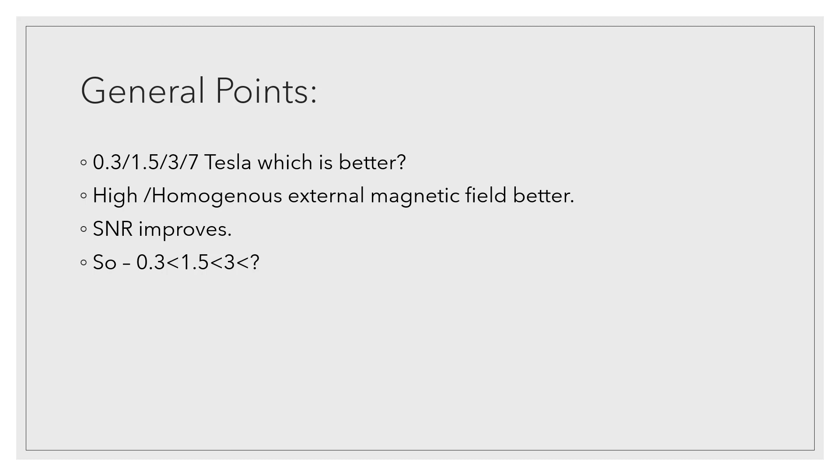General points, these are like factoids. Of course, which is better? Seven Tesla is better, but more than the field strength, homogeneity is the most important factor. You will have a better image, better data, better histogram in a 1.5 Tesla with homogeneous field rather than a 3 Tesla with an inhomogeneous field. Just remember that. But higher Tesla will improve the signal-to-noise ratios. Previously 0.3T is the least, 1.5T is better, and 3T is better than 1.5T. 0.3 will have the least signal-to-noise ratio.